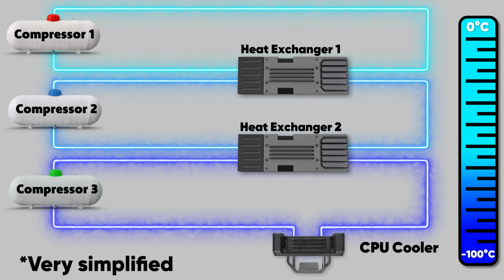Correct. One uses the first stage to chill the hot side of the second stage to -40. Then one uses the cold side of the second stage at -80 to cool the hot side of the third stage, which is at -80 Celsius.